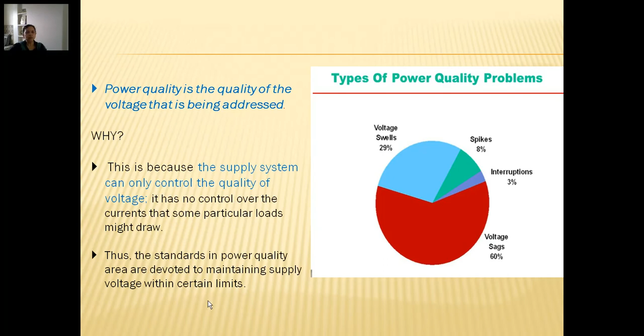And so if we start looking at most of the problems, though we are defining that power quality could be because of voltage quality or current quality, but it is mainly taken as the quality of voltage because majority of the problems are caused because of the voltage. Because the voltage is given by the supply system as per their guarantees in the specified magnitude range and the frequency ranges, any variation in this voltage is surely causing the problem for the equipment operations. It draws different currents from the same supply system, and so how much current the equipment will be drawing and what would be the nature of that current is solely dependent on nature of equipment which it is operating. And so it is termed that most of the problems are mainly caused by voltage quality. And so if you see the previous slide, you will see that power quality is equivalent to voltage quality, which is a rough definition of power quality, though it is surely a product of voltage and current both.